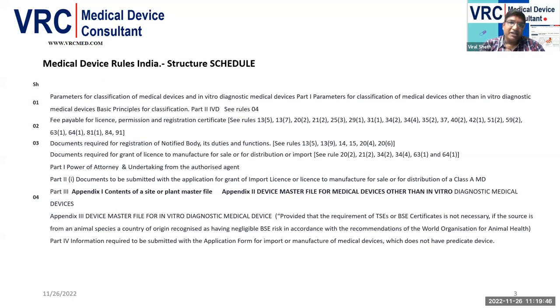In India, all medical devices are ready-made available on the SUGAM CDSCO website, which defines the intended use, name of the device, and classification. Still, if you think your device is not there, you can go through these principles and mechanisms to classify your device. Schedule 2 defines the fees payable depending on the rules applicable and depending on the class of the device.